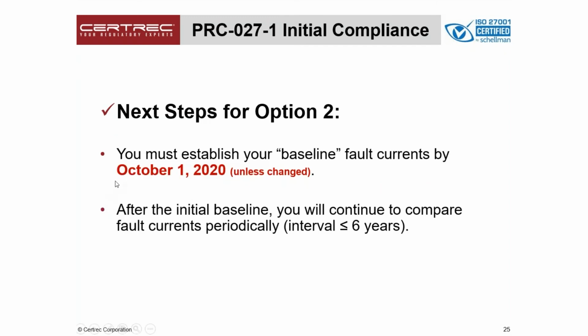For option 2, you must establish your baseline fault currents by October 1st of this year, of 2020. Again, unless it's changed. After the initial baseline, you'll have to continually compare fault currents periodically. You cannot exceed 6 years of not looking at your baseline to new data. And the other thing is, you don't want to wait to the 6th year or just before the 6th year, because if you do have a 15% greater change, then you'll be required to do a study quickly, which you don't want to get into.